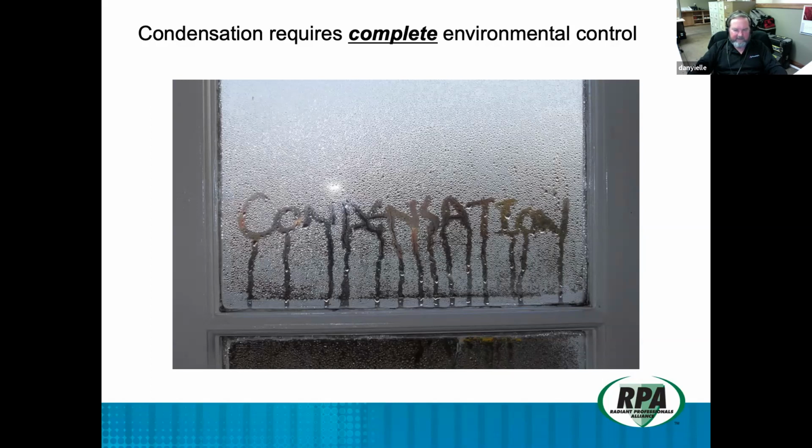I've seen a lot of buildings that have radiant floor cooling systems in them. Was in one in Calgary, Canada. It's an airport up there. And I could actually see where the tubing was. And when I asked Robert Mean about it, he said, yeah, I'm familiar with that. They let their humidity get out of control once. And that's basically what happened, the marble tile basically absorbed the moisture at that point. And you can see the tube traces, but it was no big deal. They corrected it pretty quickly.